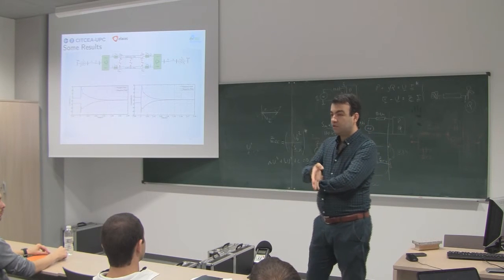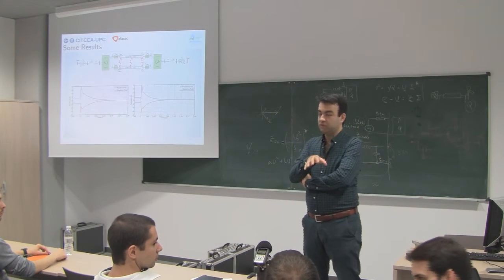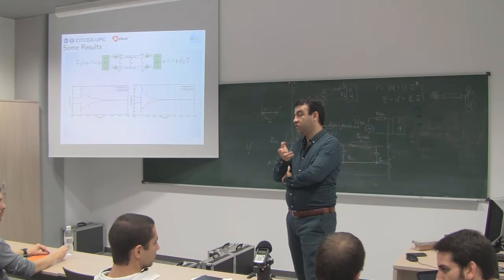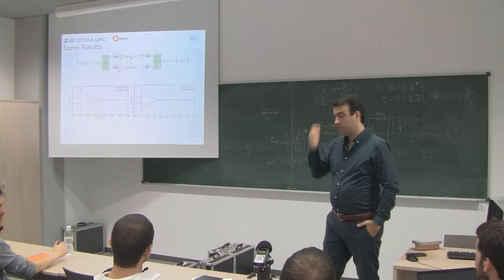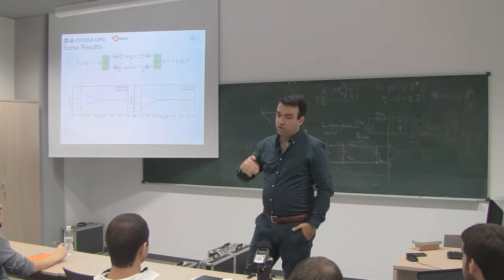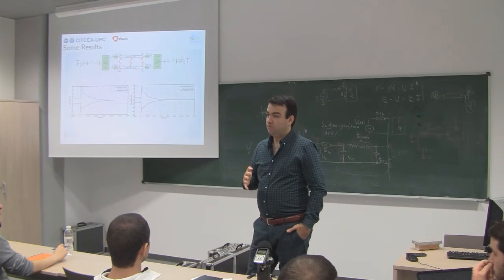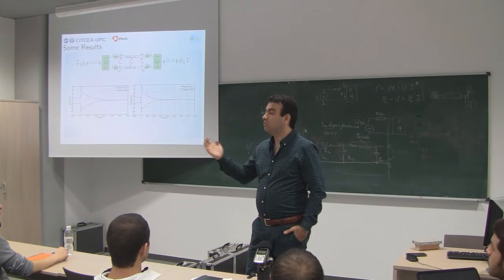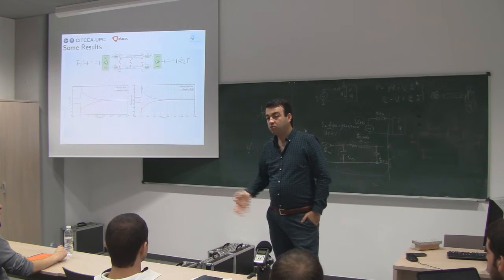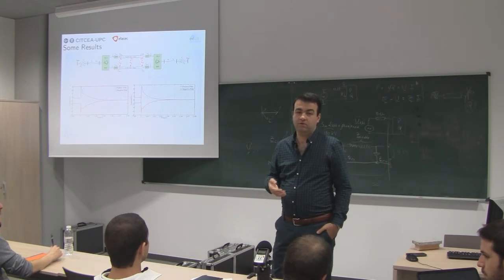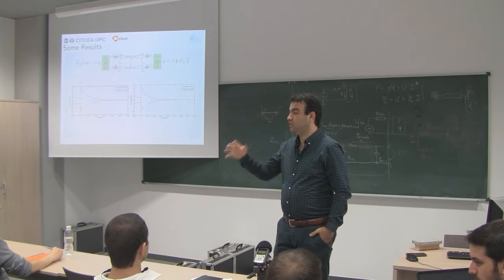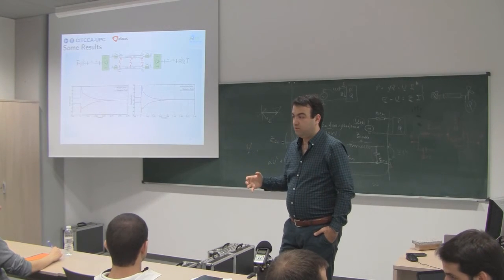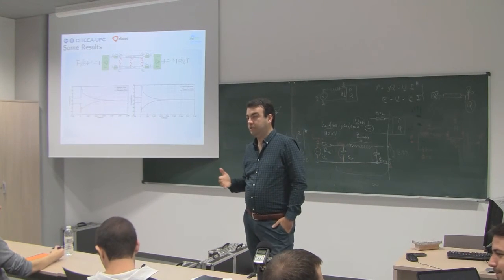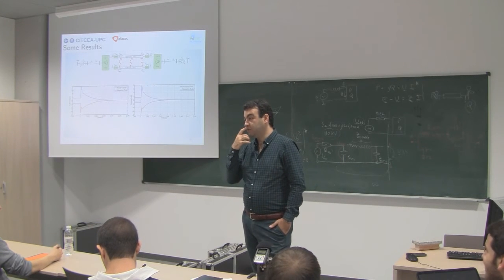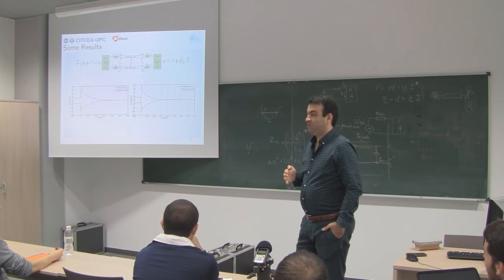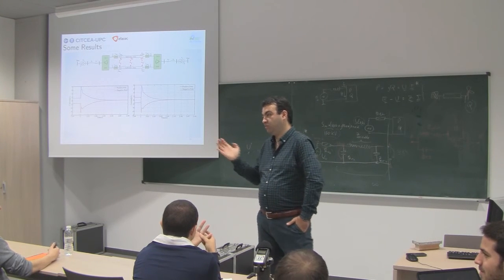But today, there is no requirement to have this in operation because we don't have such a multi-terminal grid. And this is a matter of business also, because we cannot have one topology. We should think about a kind of interoperability in future. If we are supposed to see the multi-terminal HVDC grid, we might also see different HVDC circuit breakers, as we can see different converters, because the HVDC leaders are each developing and introducing their own approaches. So it's not about selecting one topology. You should think about all of them.